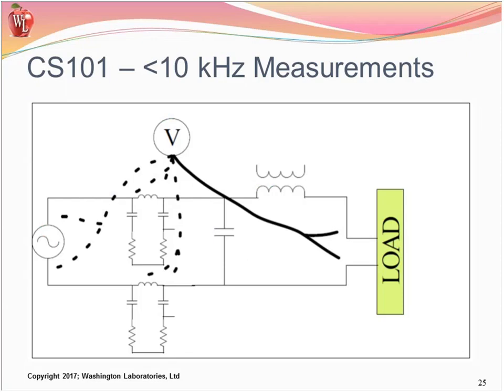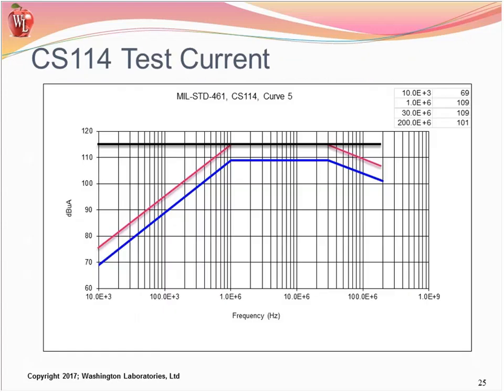My primary goal is to measure what I'm dropping across the load circuit. But also, if I don't attain that voltage by the time I get to the drive level, I need to measure what's going on across the LISN, across the power source, etc., and eliminate these problems so the test voltage is maintained across the load. Remember, this is a test configuration detail, not an actual installation, so these allow you to get to a more prevalent test level.